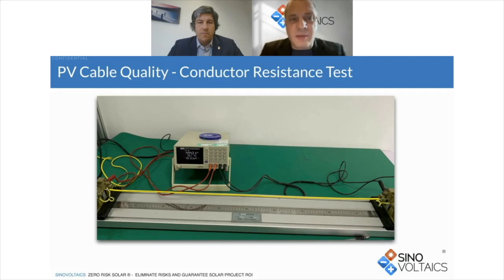One of the common and important tests is the conductor resistance test in line with the applicable cable cross-section. So at a given temperature, the resistance of the conductor, which is usually made of either aluminum or tin-coated copper, needs to meet a certain value. If resistance is too high, then simply speaking, and in line with Ohm's law, there is a higher impedance on the current flow, and therefore the cable is less electrically conductive, and there are also transmission losses. So it also means there's more heat. And this is one of the quality issues our team encounters with bad quality workmanship at cable factories.